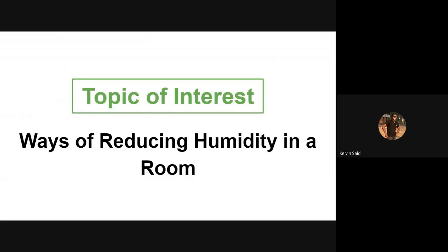So in order to avoid this contamination, I would recommend doing the refilling process in a room only if the humidity is below 50%. This is because the moisture content below this humidity level doesn't affect the zeolite performance. Before refilling zeolite, you need to check the humidity level of your room by using a humidity monitor. You can buy one of these monitors for about $20 on Amazon.